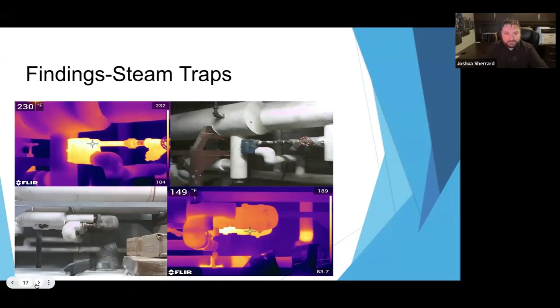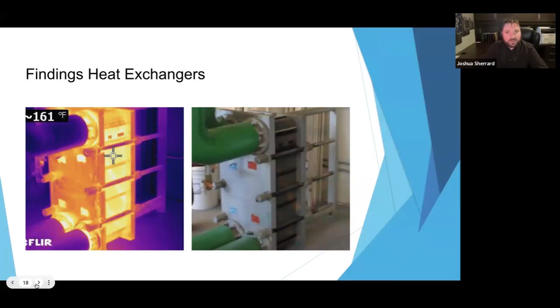Heat exchangers are another example of common components within the mechanical system that can be insulated with mechanical insulation, where we see huge savings. With pumps, we see facilities where each pump saves $300 to $500 a year. When you look at a pulp mill, they could have hundreds and hundreds of pumps throughout their system, so it doesn't take long for those savings to add up. The same goes for heat exchangers. As we try to become more sustainable long-term in the current climate we're in, every bit helps with becoming more efficient.